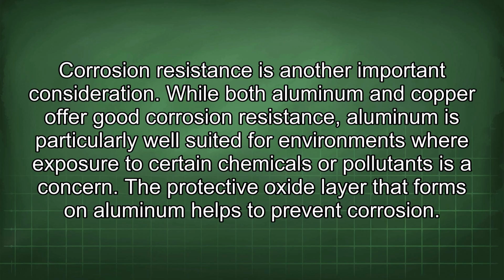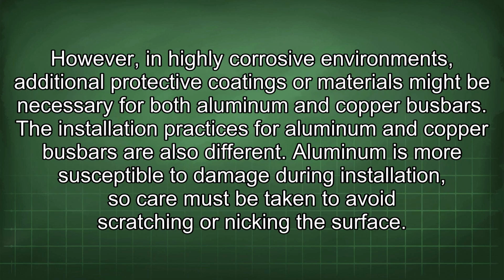Corrosion resistance is another important consideration. While both aluminum and copper offer good corrosion resistance, aluminum is particularly well suited for environments where exposure to certain chemicals or pollutants is a concern. The protective oxide layer that forms on aluminum helps to prevent corrosion. However, in highly corrosive environments, additional protective coatings or materials might be necessary for both aluminum and copper busbars.